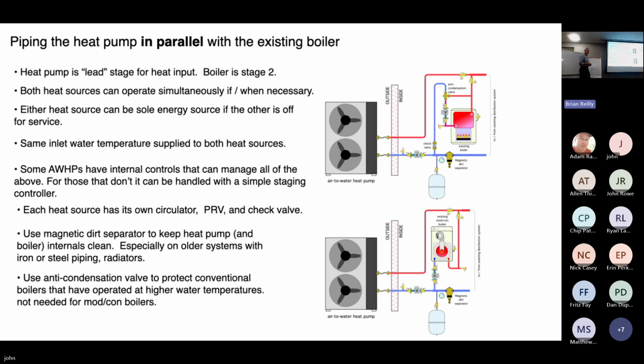Yep, you go backwards through the circulator that's off. A standard circulator without a check valve, water can flow through it either direction. And basically what'll happen, instead of all your flow going out to your load, some of it is going to go in reverse through the inactive circulator. So many of the small circulators today come with the little plastic check valves. If you have a circulator that doesn't have that, you can use an external spring-loaded check valve.